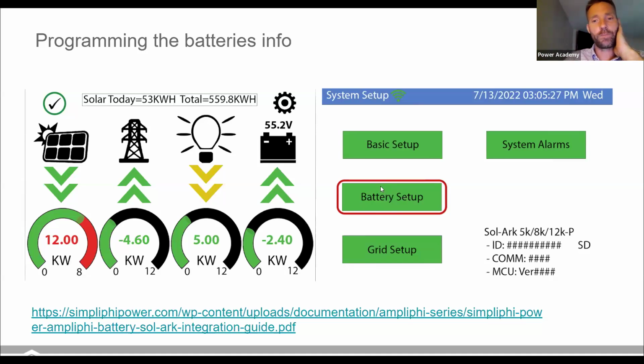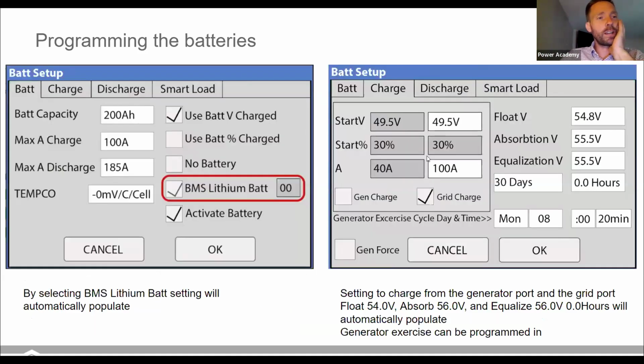We're going to go into battery setup. Under battery setup, you're going to have a number of different options. If you're using one of our communicating batteries, you want to make sure to have a checkbox on the BMS lithium battery. The default address there is just 00 for Briggs batteries. Activate battery allows the inverter to start up the battery if the battery has gone through a low battery cutout.